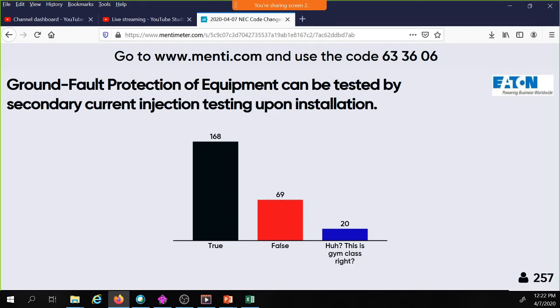And I'm going to read, and this language didn't change in the 20 cycle, but here's what it says in 230.95. I know everybody has their code books, and they're opening to 230.95(C). It says the ground fault protection system shall be performance tested when first installed on site. This testing shall be conducted by a qualified person using a test process of primary current injection in accordance with instructions that shall be provided with the equipment. So secondary current injection testing is no longer permitted. It has to be primary current injection testing if you're on the 17 code, not the 2020 code. And most of those people in this photo are probably on the 17 code.